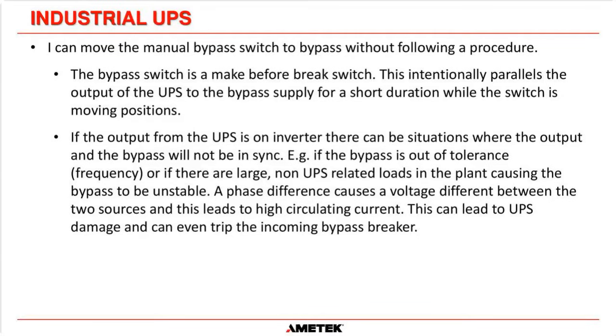If the output from the UPS is on inverter, then there can be a situation where the inverter output and the bypass may not be in sync, and that could be instantaneous. So if the bypass is out of tolerance frequency-wise, or if there are large non-UPS related loads in the plant causing the bypass to be unstable, the phase difference could cause a voltage difference between the two sources, and that would lead to high circulating current. And that could lead to either the IGBTs blowing up, or it could even trip the incoming bypass breaker because there's too much current.